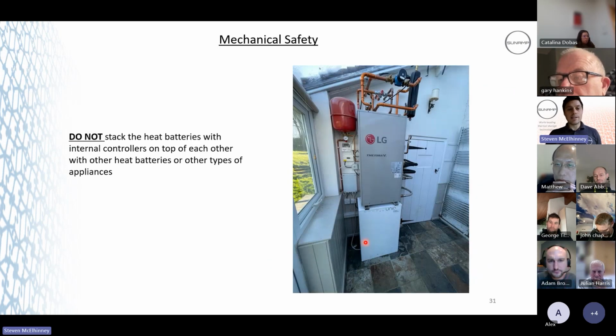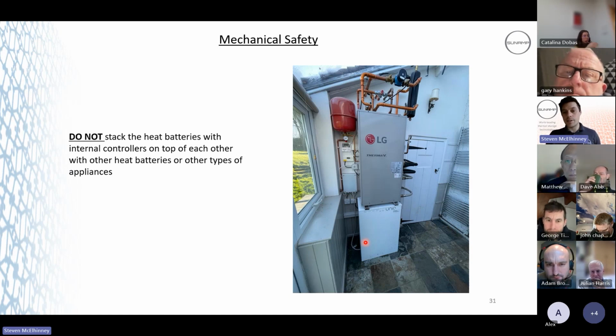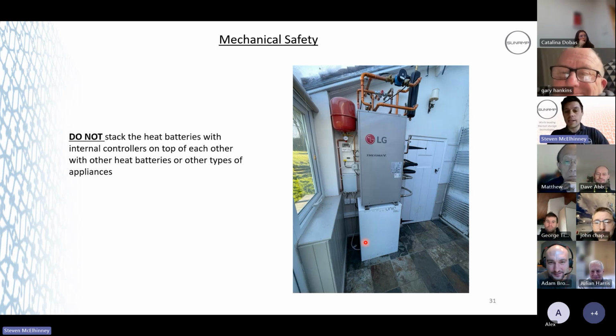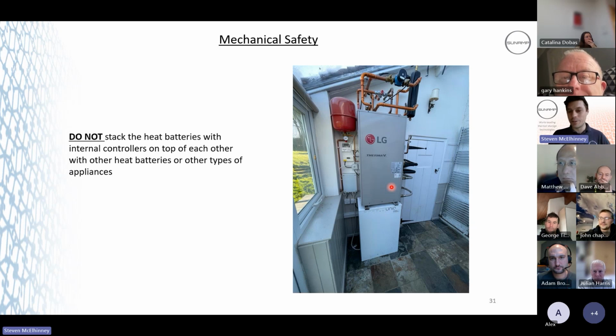Don't stack the heat batteries with internal controllers. I mean, why you would want that in your house anyway is beyond me. That's monstrous. You've got plenty of space there on the floor to have that set up. But yeah, we do have some components inside the battery. We've got relays, PCBs, and a temperature sensor. If you've got to work on that, you'd have to remove that heat pump. So you're going to have to get someone who's F-gas qualified to decommission the heat pump to do a 2-minute job, possibly on the top of the battery. So, don't stack them.